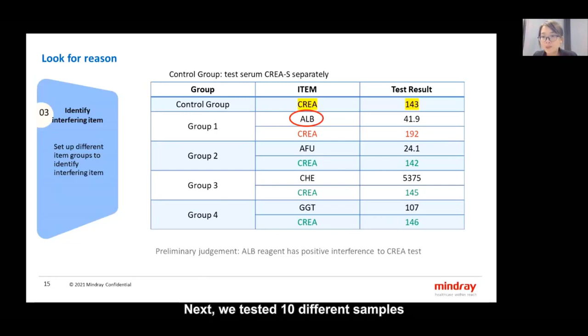Next, we tested 10 different samples for verification. Firstly, in this table we can see the relative bias percent is obvious. And after we add a special wash between ALB and the creatinine test, the relative bias turns smaller. It was confirmed that ALB reagent has a positive interference to the creatinine test. And after modifying the ALB reagent testing sequence, the issue was solved.